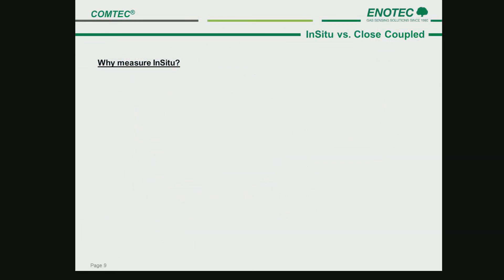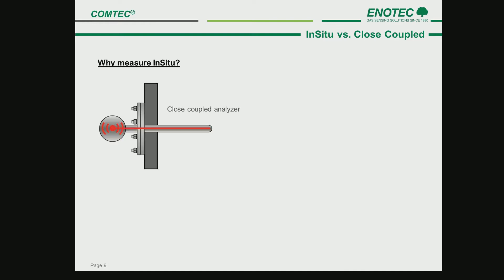So why does Enotec measure in situ? What are the benefits? Most manufacturers on the world market produce O2 COE analyzers which measure close-coupled, sometimes referred to as quasi in situ. These analyzers have sensors installed in the terminal box of the probe outside of the process and need to control the pressure, temperature, and contaminants within the terminal box. The sample gas is sucked from the process to the sensors, usually with an aspirator. The filters will block in dusty applications as the suction forces particulate into the filter pores.